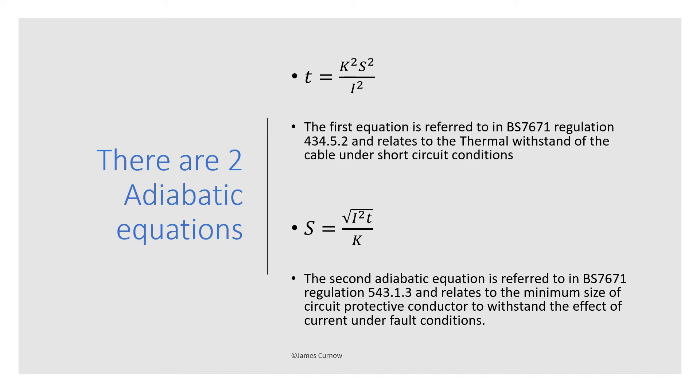The equation at the bottom is referred to in regulation 543.1.3 and this relates to the minimum size of the circuit protective conductor to withstand the effects of current under the fault conditions, so this will give you the minimum size of conductor for the CPC.